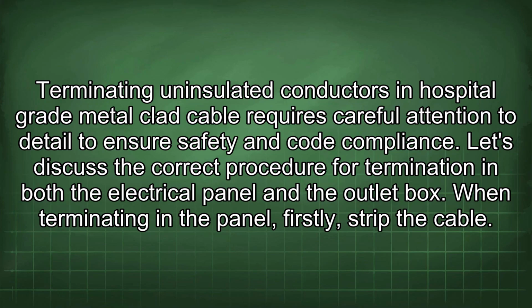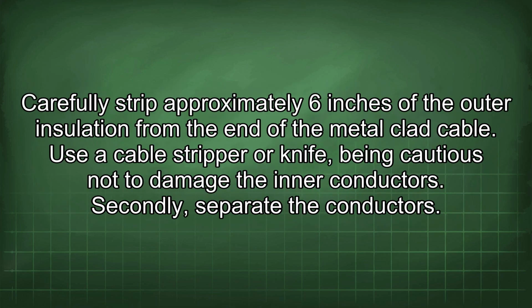Terminating uninsulated conductors in hospital-grade metal-clad cable requires careful attention to detail to ensure safety and code compliance. Let's discuss the correct procedure for termination in both the electrical panel and the outlet box. When terminating in the panel, firstly, strip the cable. Carefully strip approximately 6 inches of the outer insulation from the end of the metal-clad cable. Use a cable stripper or knife, being cautious not to damage the inner conductors.